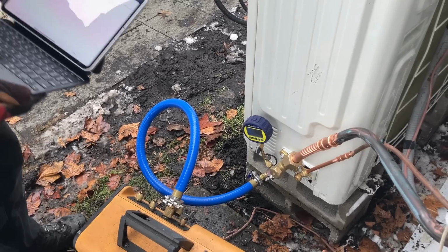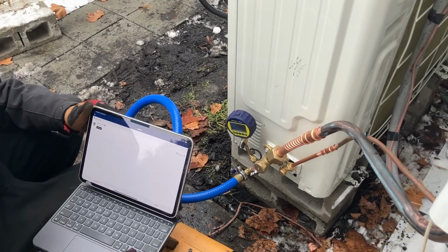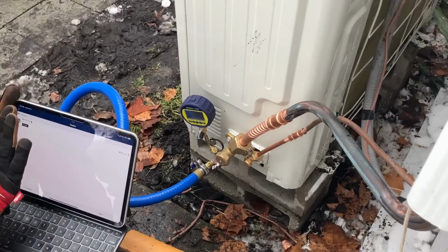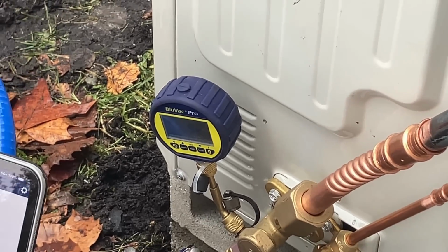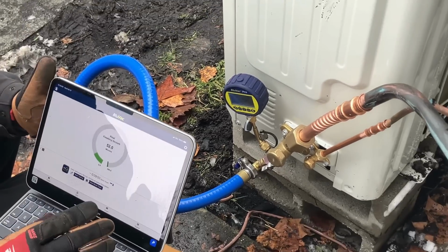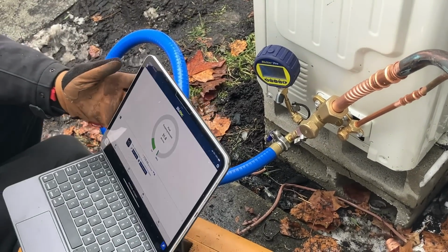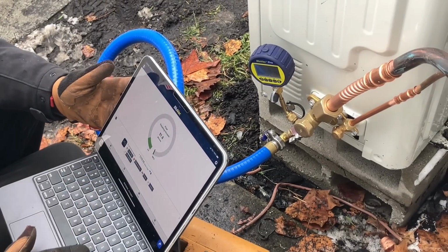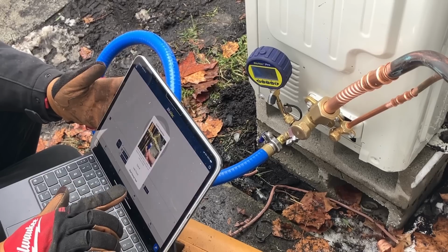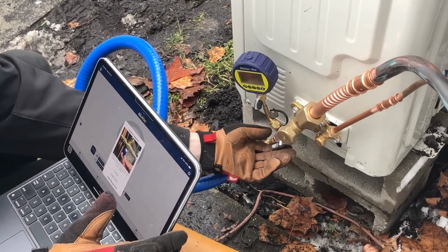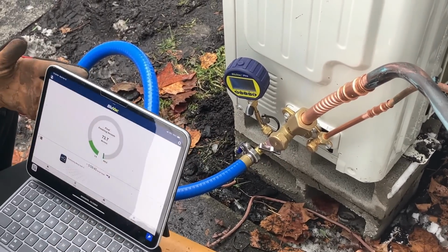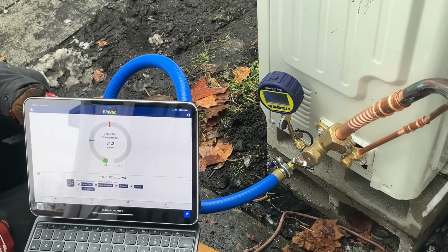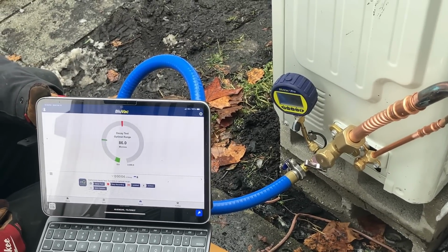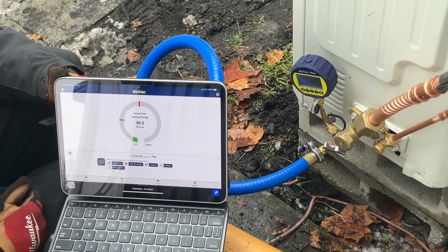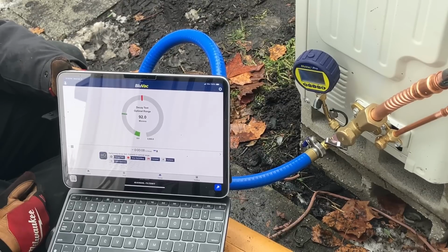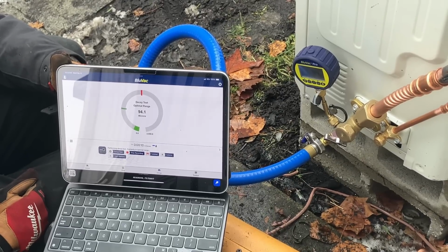All right, we've been vacuuming down for about 15 minutes. We are at 53, 52 microns. We're gonna do a decay test right now. We're gonna close that service valve on our 7/8. We're gonna close the recovery valve. There you go, we're jumped up. We're at 79, 80, 83, 85, 86. We're doing a decay test. We're gonna see how high this goes, and if it passes, we're golden.